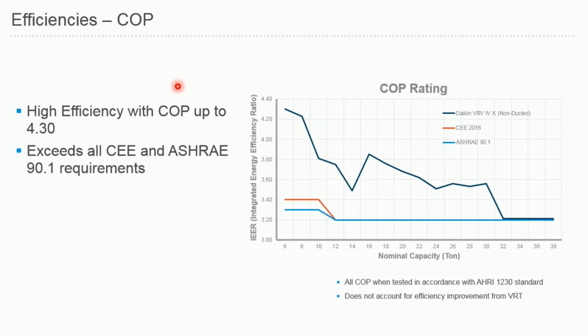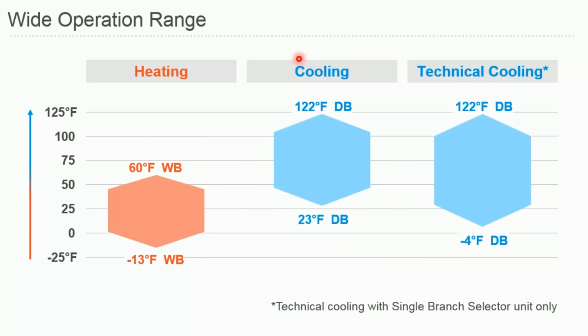And the same goes for COP. The highest COP is 4.3, and there are still some increases happening, especially at low COP ratings, with the additional K-type vapor injection compressors, and we're still obviously satisfying the ASHRAE and CEE requirements there.